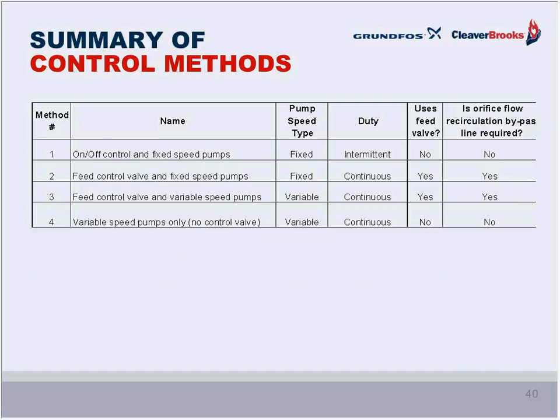Okay, so there's our summary of our control methods. We've got a couple of fixed speed solutions, a couple of variable speed solutions. The first one is intermittent duty. The rest of these are continuous. Some require feed valves, some don't. Some have recirculation lines, some don't. And all of this has a pretty significant impact on the boiler feed pump equipment that gets selected at the end of the day.